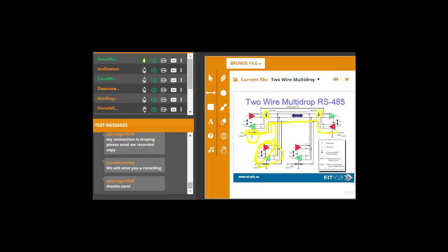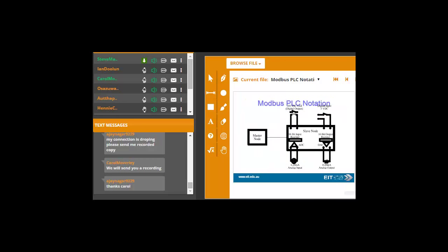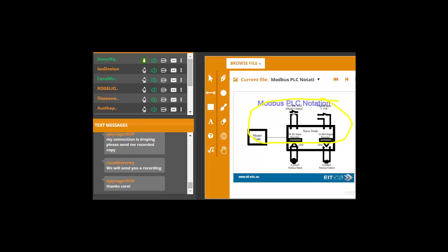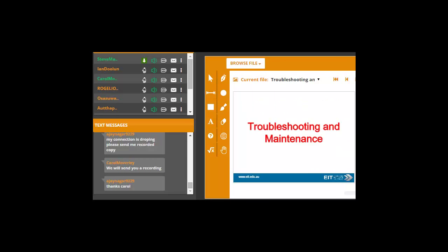One of the challenges also with these links is always make sure you go to terminating resistors there at the ends of the cable to prevent reflections. Sometimes they've come off, I've noticed on some devices. And as I said, if you can at all costs, try and avoid using 485 and go for a good old fiber optic link. Now just to briefly talk about Modbus as one of the protocols used. You'll always hear Modbus running over 485. Modbus, very easy to use. Some of the challenges with Modbus are if you get any errors in the link due to interference, you could find your messages are just ignored. But very easy to use and very easy to troubleshoot Modbus. That's very well defined. Extremely good standard.